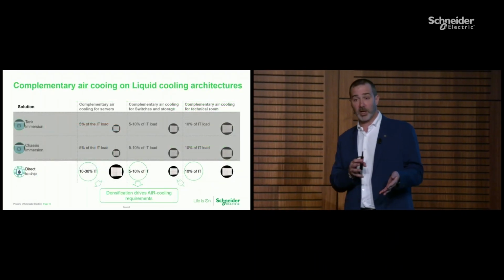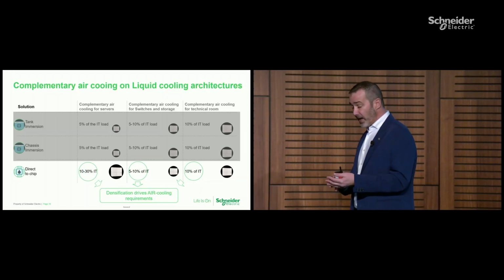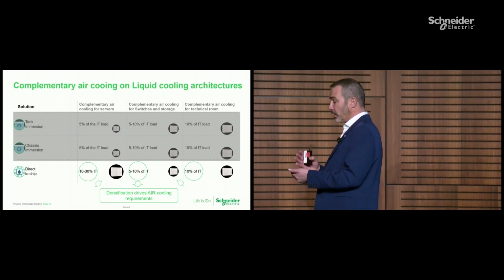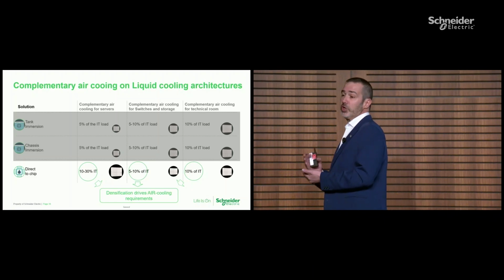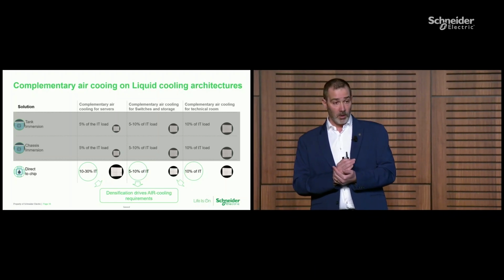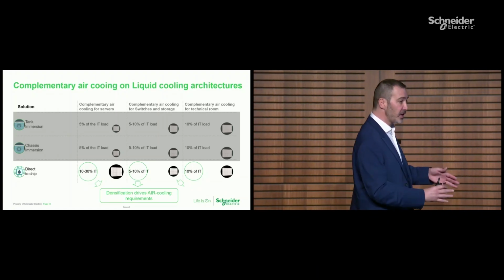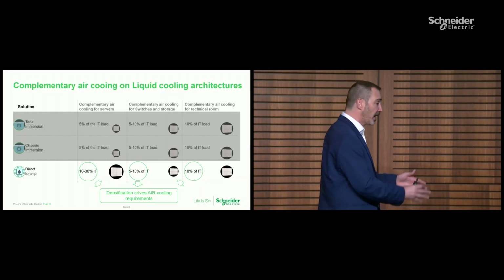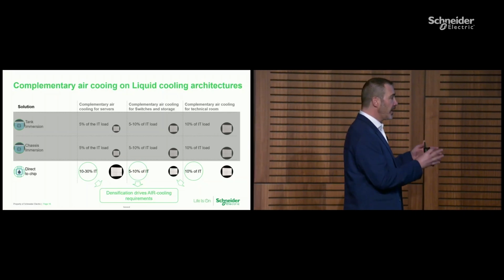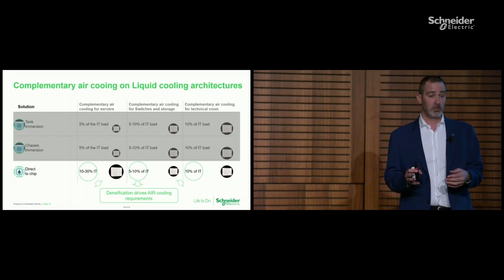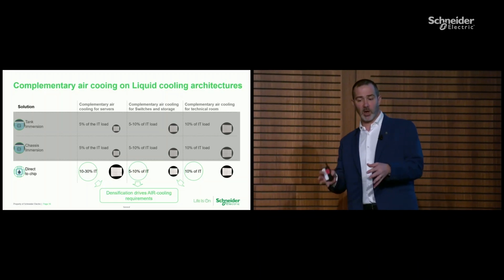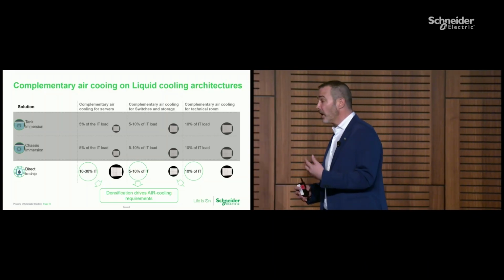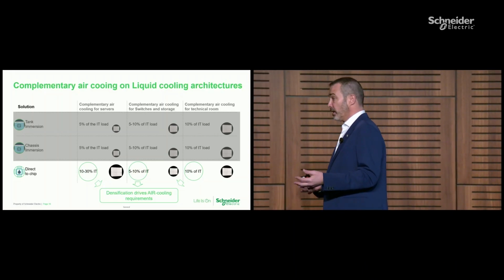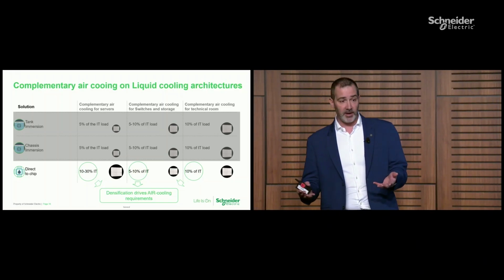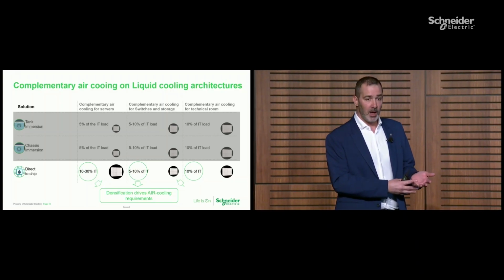Last but not least, the cold plate direct-to-chip cools the chip, which means that everything else in the white space, in the rack, in the system, needs to be air-cooled. So air remains in the equation. There is no discussion around that. Of course, the percentage is much less than the full percent we have today. However...